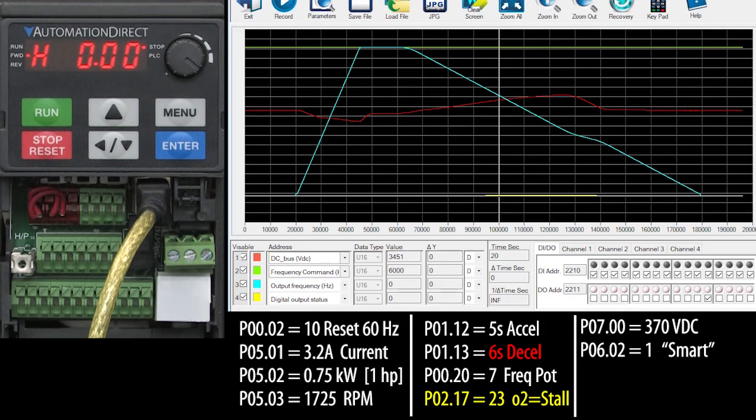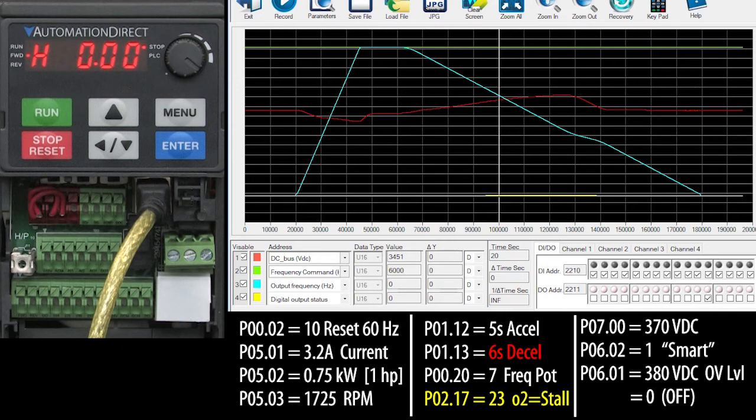Could I have turned this automatic stall prevention OFF and just set the deceleration myself? Sure. You do that by setting parameter 6.01 to a zero. I did that and I found I had to set the deceleration to 22 seconds to prevent an overvoltage fault.